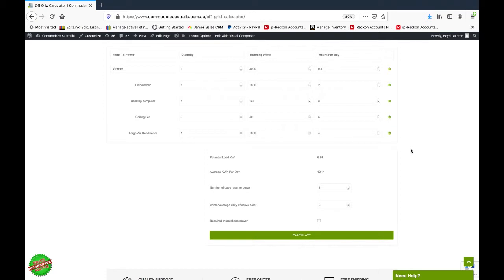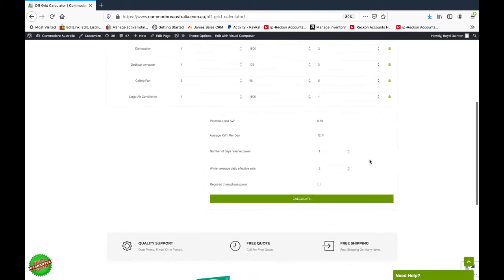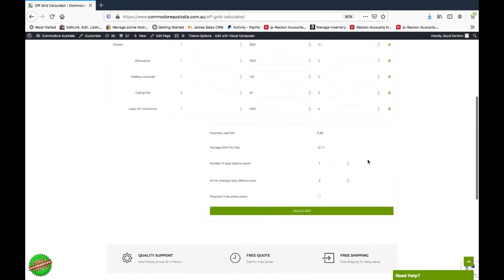We've then got our average kilowatt hours per day. We work that out by going quantity times the running watts times the hours per day, and we then add all those up together to get our average kilowatt hours per day.